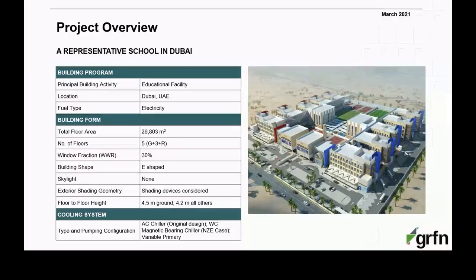For the cooling system, the original design was air-cooled chillers. For the net zero energy case, we have modeled a water-cooled chiller, a magnetic bearing water-cooled chiller. In both cases, there were variable primary, but in the net zero energy case, the delta T was a little bit higher, mainly to reduce the pumping power.